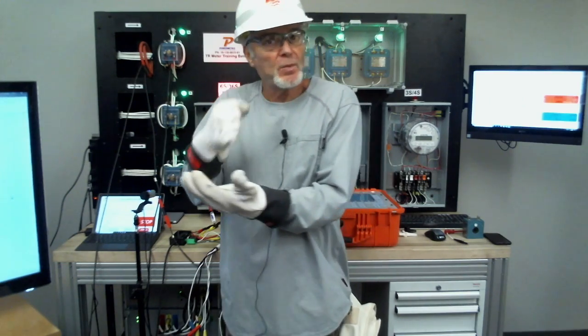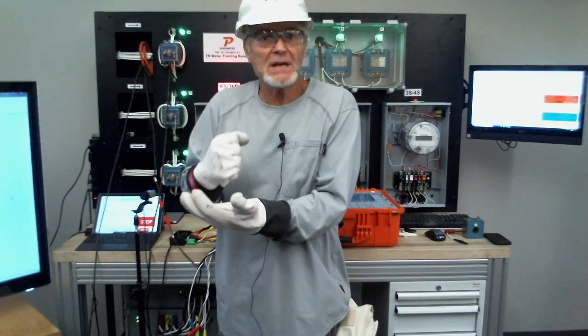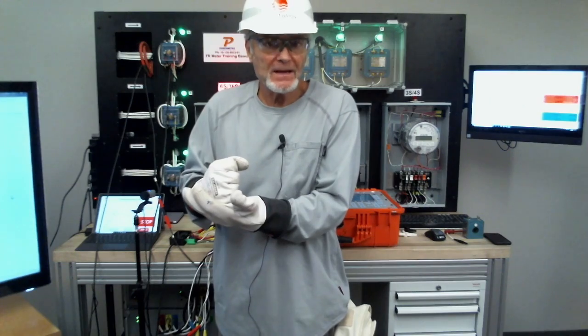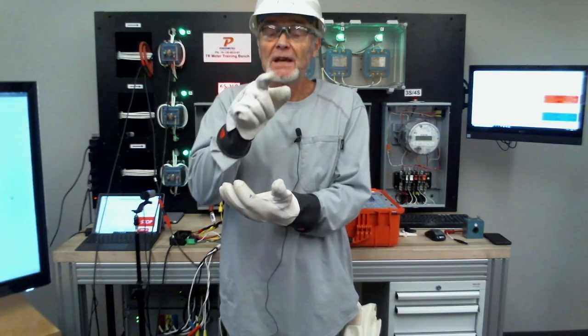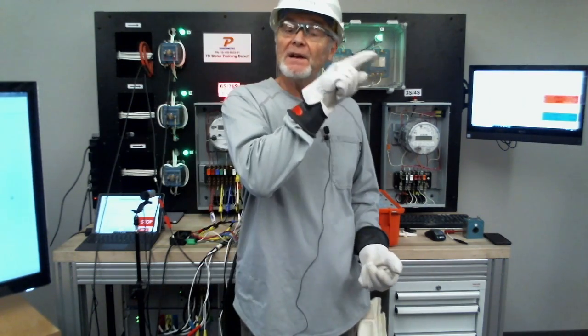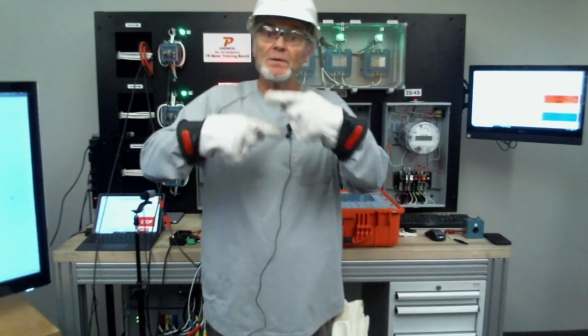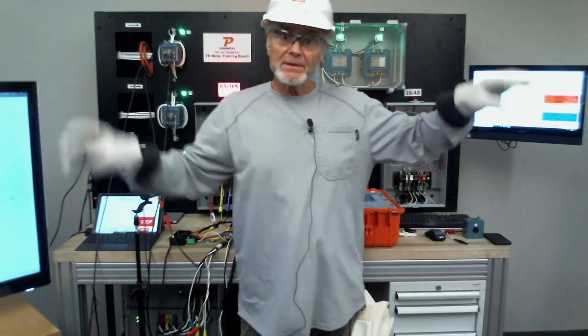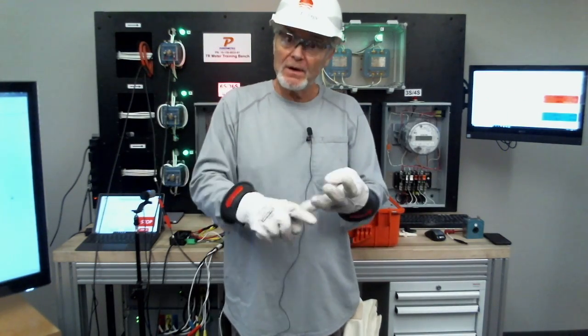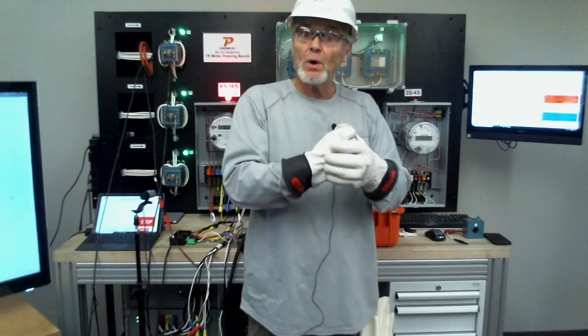When you're doing a load box or a benchtop test, make sure you're connected into probe set 1. If you're connected into probe set 2, it's going to tell you it's not seeing any primary current. It'll act just like showing up at a site where they don't have enough load there. Like in all the webinars we've done, it gives you Danger Will Robinson, one error after another.